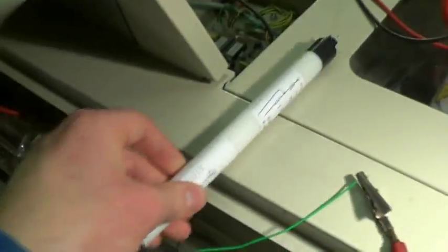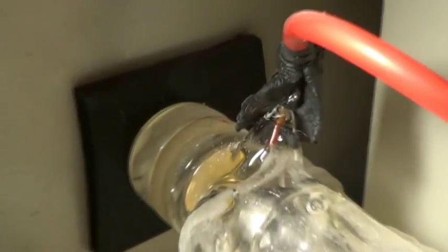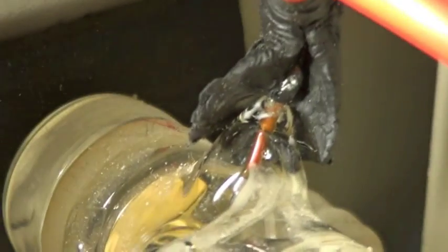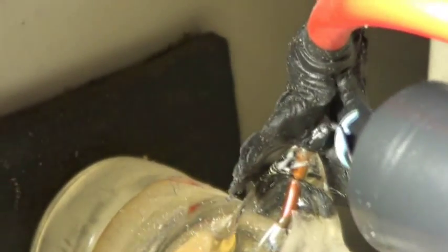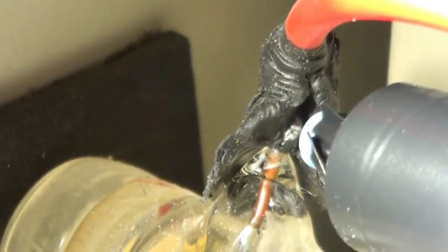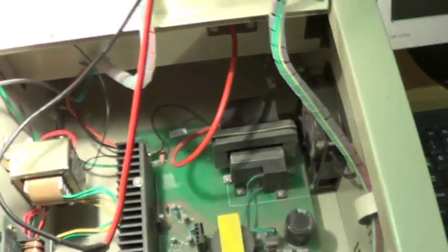The divider tip will be touched to the tube anode. I've cut away some of the insulation so you can see the bare metal there. So that's going to be touched just like that. The negative return of the divider here goes to the bottom end of the tube. That's the bottom of the four terminal connections.